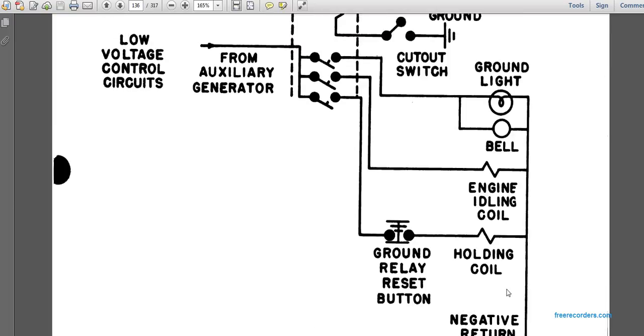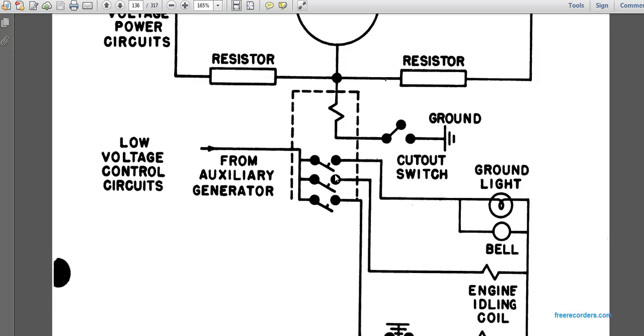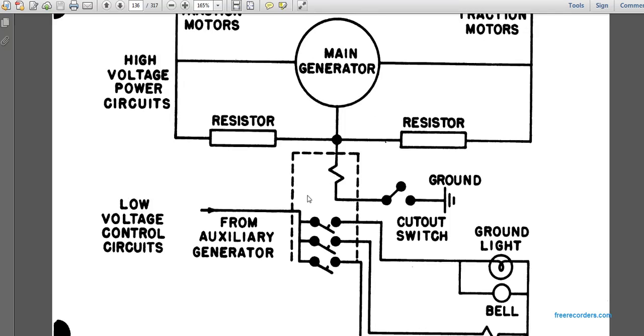This is the ground relay circuit. You can see the negative return from three different lines coming from the holding coil, the engine coil, and the bell and ground light. Around the holding coil circuit, it goes to the ground relay reset button, and there is a throw switch for each of them from the low voltage control circuit, from the auxiliary generators, for the ground light, bell, and idle engine coil on the ground. A throw switch is provided for each one of those.